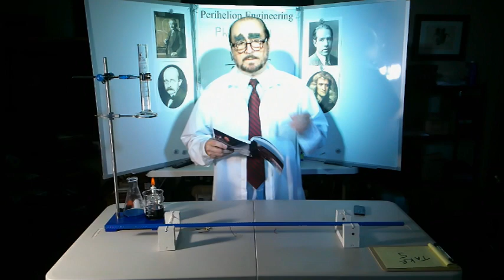Let's look deeper. In the beginning, when I put this all together, I knew that the speed of sound was somewhere around the 5,000 meter mark, you know what I mean? So I kind of knew what I was looking for, but what I didn't expect was the internal echo inside the crystal. The little tiny crystal, the signal resonates inside the crystal. So that resonation moves down the bar right along with it. So you can see when I start out and I'm just pinging at 10 hertz, just 10 little hertz, right? I ping and I listen, and I ping and I listen. Boy, I couldn't understand. There's like 3 repeats of big waves and then all kinds of bundles of little waves. Really confusing in the beginning. And then the light came on and I started to understand, okay, internal echoes in the crystal. Now Lucy's going to show you what happens.